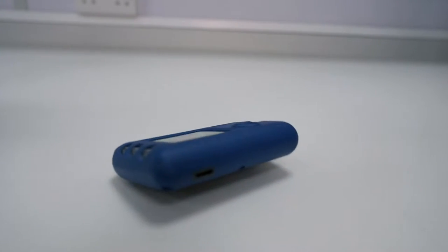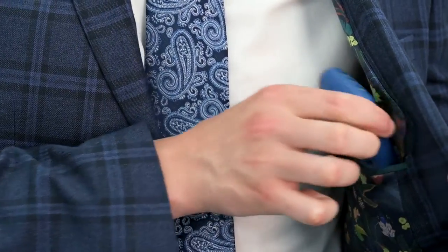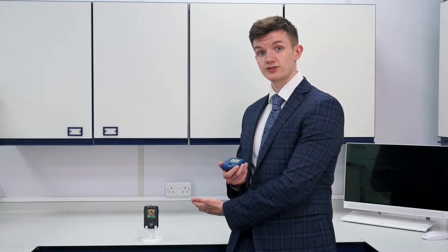The Tracerco PED is a lightweight yet highly durable personal dosimeter designed for the detection of x-ray and gamma radiation. It is encased in a shockproof hard polymer shell and will easily fit within your pocket. It comes in five models: the PED Blue, the PED Plus, the PED IS, the PED ER, and the PED ER Plus. I'll mainly be covering the PED Blue but I'll also touch on features of the other models.